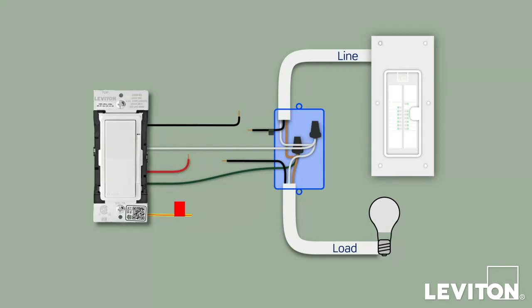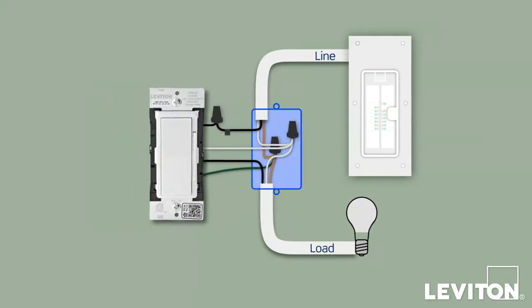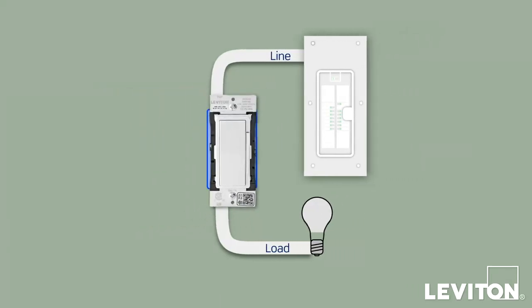Connect the load wire to the red wire on the dimmer or switch. Connect the line hot wire to the black wire. If this is a single pole installation, place a wire connector on the yellow with red stripe conductor. Tug on all of the connectors to ensure the connections are secure. Now that everything is wired, you'll test the device prior to fully mounting it in the wall box. Gently bend the wires and push them into the wall box. Partially screw the mounting screws into the wall box mounting holes.